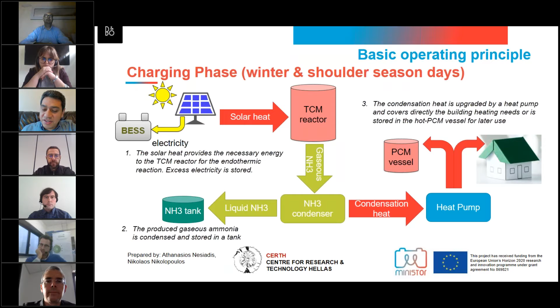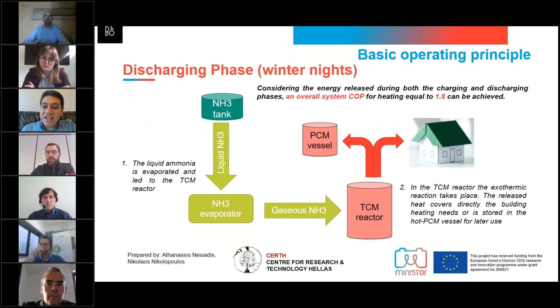In the discharging phase, in winter when there is no sunshine, the ammonia tank evaporates the liquid ammonia, which is led to the thermochemical reactor, and the evaporator turns it back into its gaseous form. The thermochemical reactor produces an exothermic reaction, and the released heat can be placed either into the heating system of the household or into a phase change material vessel if not needed, giving flexibility in its use. The coefficient of performance of the system during both charging and discharging phases has been calculated at about 1.8, making it more efficient than a simple water-based storage.